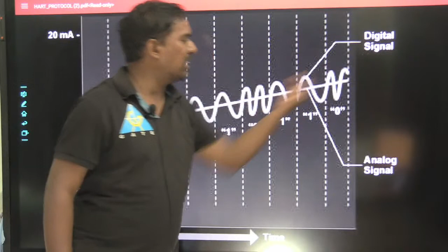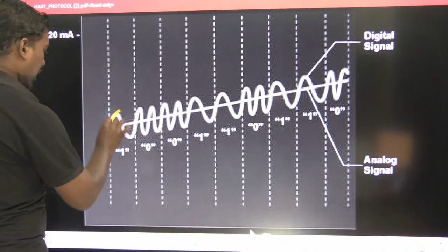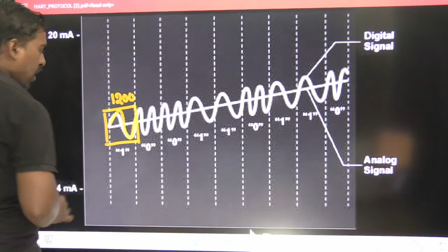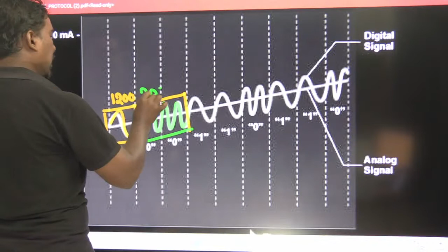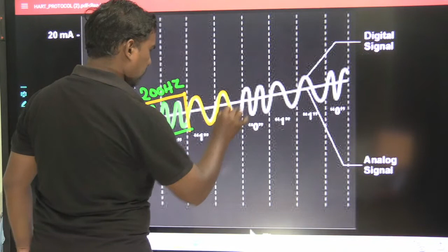On the 4 to 20 milliamperes current signal, we send the digital signal in this format - these are different frequency signals. This is 1200 Hz, one signal. And on this we send another frequency signal, a 2200 Hz signal. Wherever the 1200 Hz is taken, it is taken as 1, and the 2200 Hz is taken as 0. This is the way they send information in the form of digits - this is 1, this is 1, and this is 0, like this. They are sending in the form of bits.